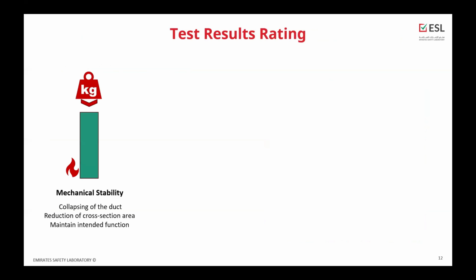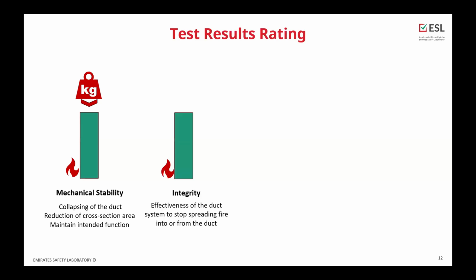We are talking about fire-rated ducts. So what does this rating mean? What stands behind these words? First of all, we have the pillar called mechanical stability. This represents the structural stability of the duct itself. So the duct under test, inside the furnace and outside the furnace, cannot collapse. The reduction of the cross-section area has to be within the stated limits, and the duct shall maintain its intended function. Also, for the smoke extraction duct, there shouldn't be any gaps developed on the duct surface which decrease its capability for smoke extraction.